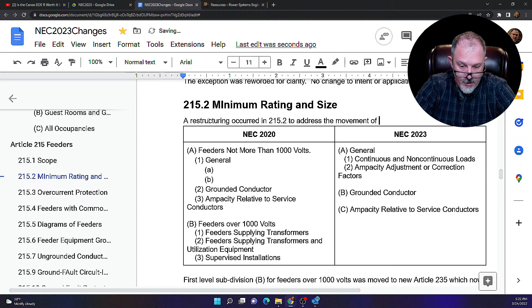Okay, and then the grounded conductor, and then the ampacity, that became a B and a C. So we have 3 first level subdivisions now in 215.2. The first level subdivision A titled general, we have 2 second level subdivisions titled continuous and non-continuous loads, and ampacity adjustment or correction factors. We did not change the intent nor the requirements, but we did restructure.